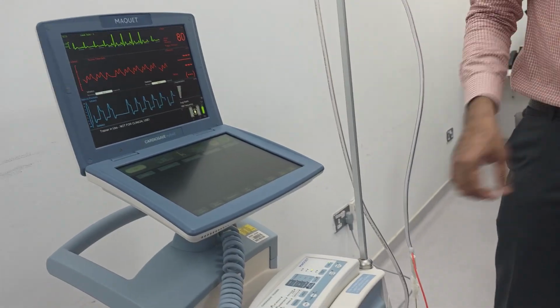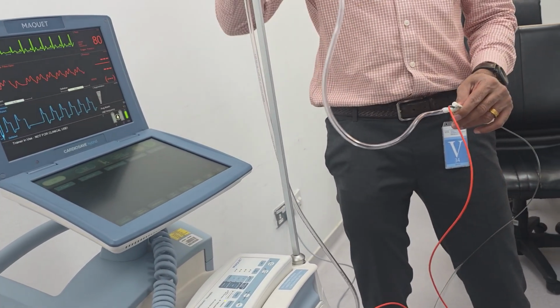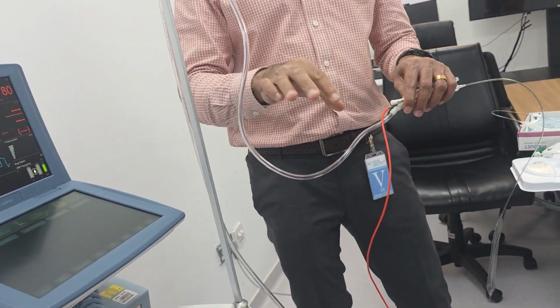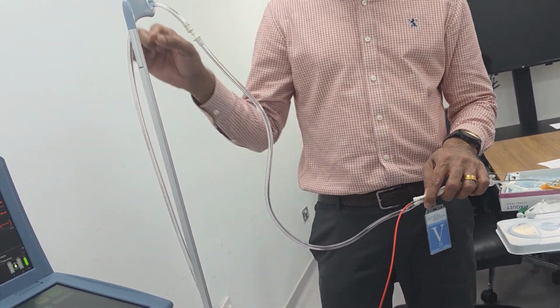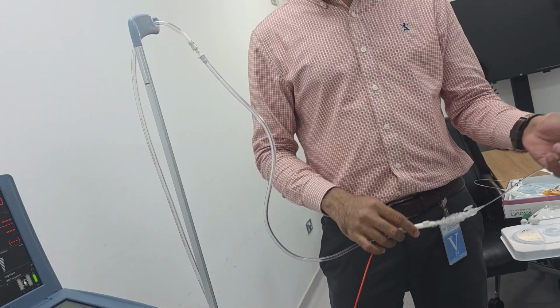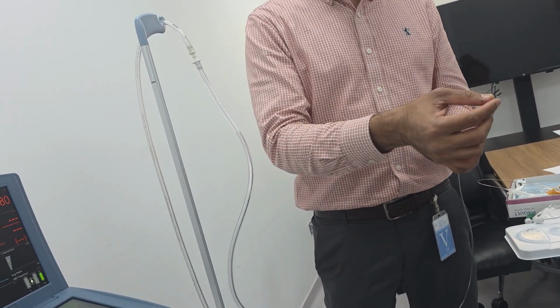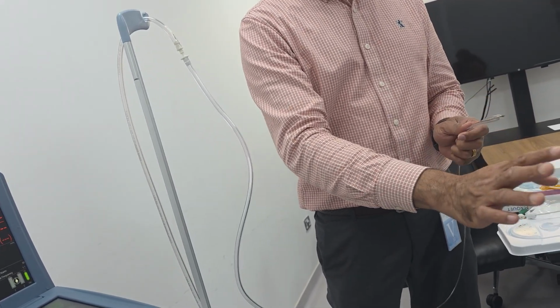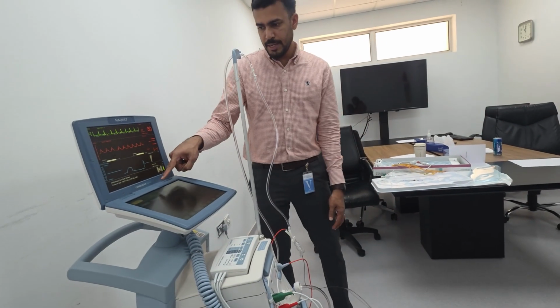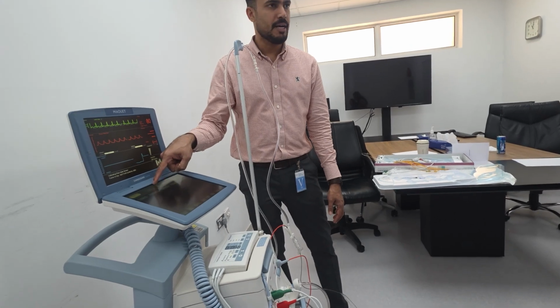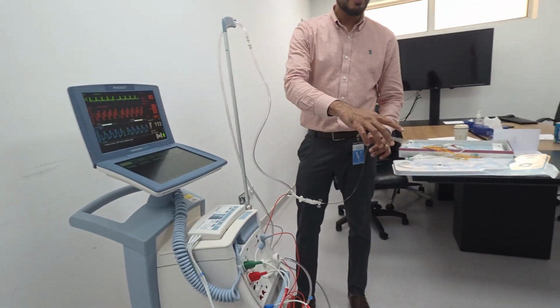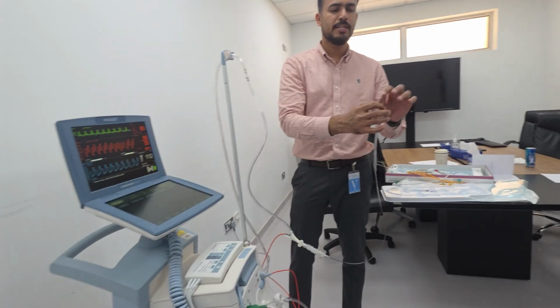And here the fiber, you are still connecting to the saline bag. You don't need to connect the transducer, but it should be connected to a saline bag with a pressure of 300 mmHg, and there should be a flow of 3 ml per hour to the patient side. That's the recommendation. Now this is important. You can see it's a hybrid mode, same like hybrid cars. It will work just to maintain the 3 ml flow to the patient side. The inner lumen needs to be activated.